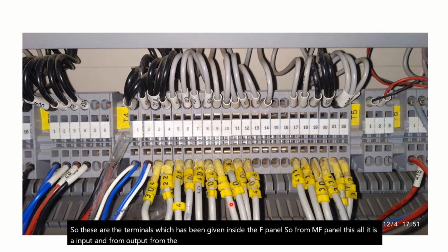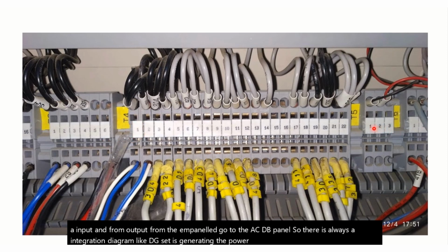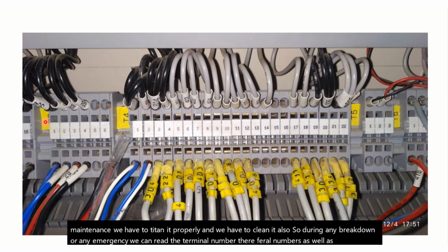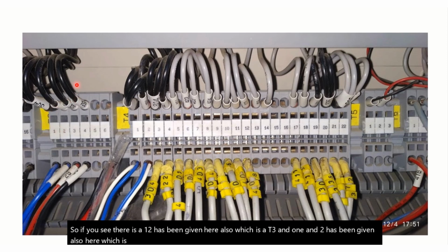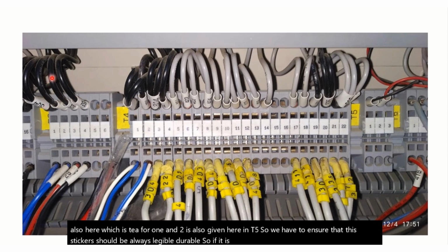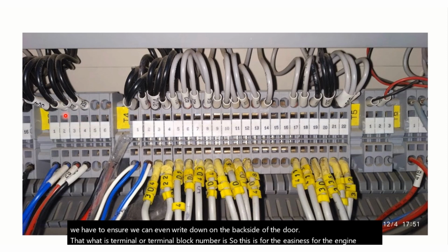So all these cables and wires, during preventive maintenance, we have to tighten properly, and we have to clean them also. So during any breakdown or emergency, we can read the terminal numbers, their ferrule numbers, as well as the entire TB number. If we see, there is a 1 2 given here, which is T3, and 1 and 2 given here, which is T4. 1 and 2 is also given here in T5. So we have to ensure that these stickers are always legible and durable. If they are worn out or torn, then we cannot make out which 1 2 we are talking about from the diagram. So we have to ensure this, or we can even write on the back side of the door what this terminal or terminal block number is. This is for the ease of the engine operator, because he has to deal with all this wiring during an emergency.